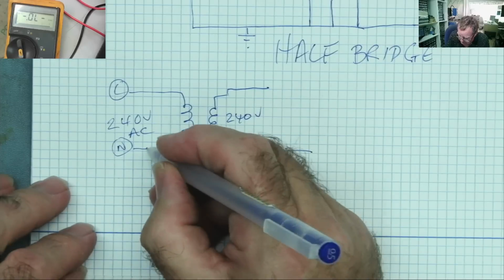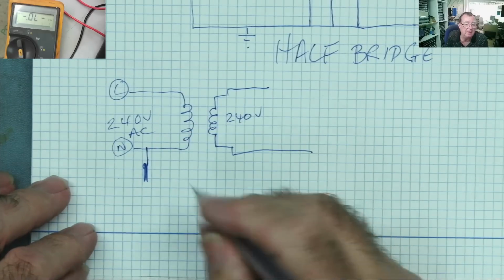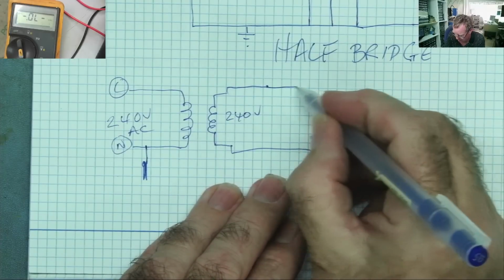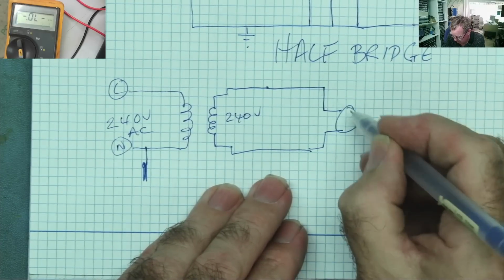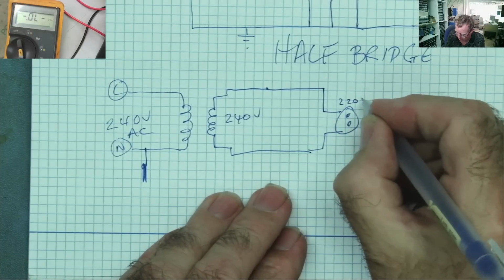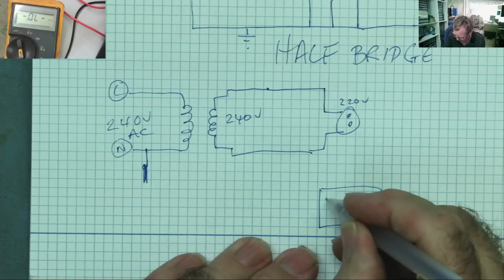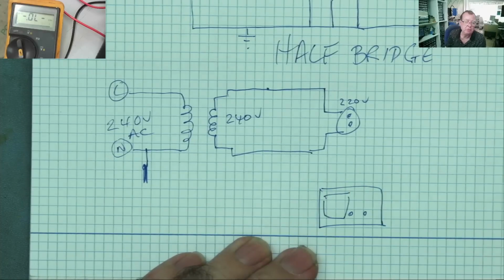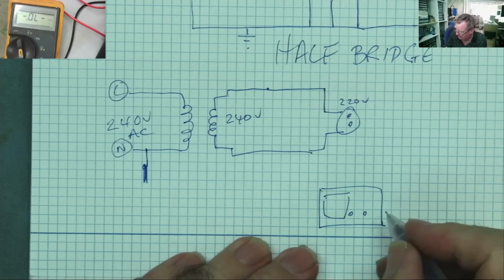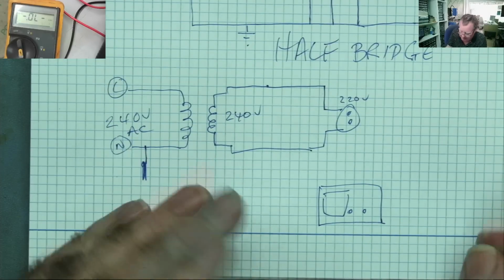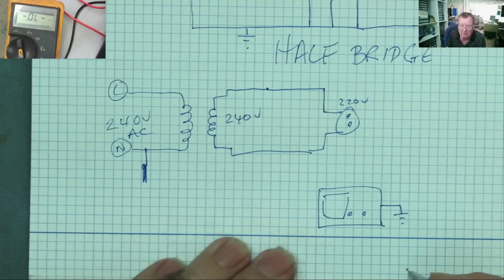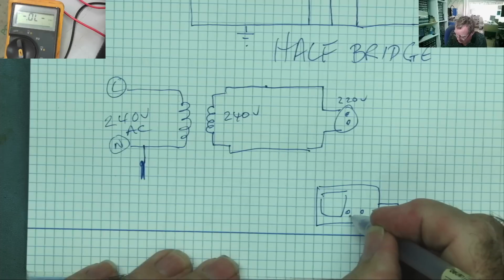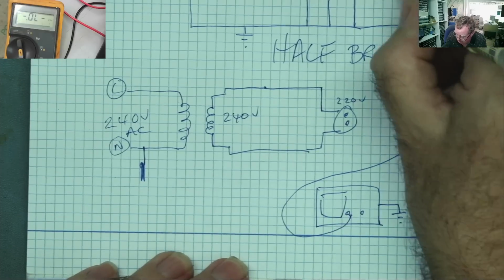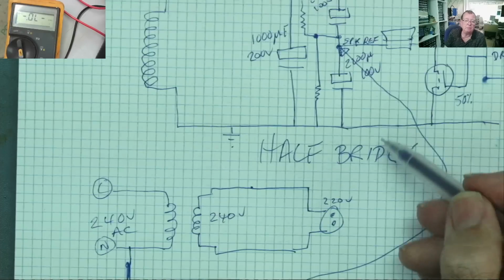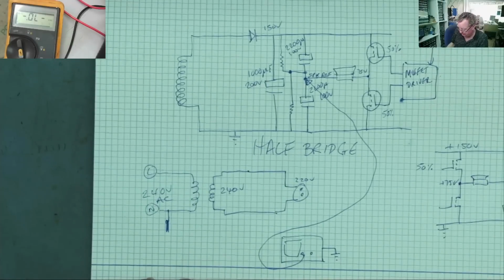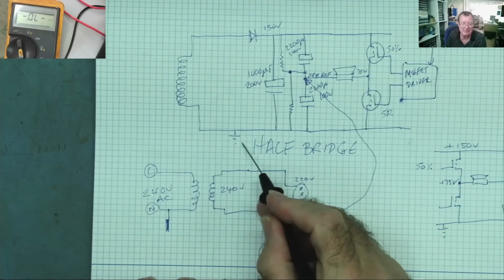So the mains neutral is connected to ground, we know this. On this side of the transformer nothing is connected to ground. This then goes to a socket, and that's where I plug in anything I want to work on. My scope is plugged into a normal main socket, as is all the rest of the equipment on the bench, unless it's battery powered or through something like a USB type power supply. But this scope is grounded. So when I connected that point to here, I did ground this point, but because of the isolation transformer, this ground is not connected.